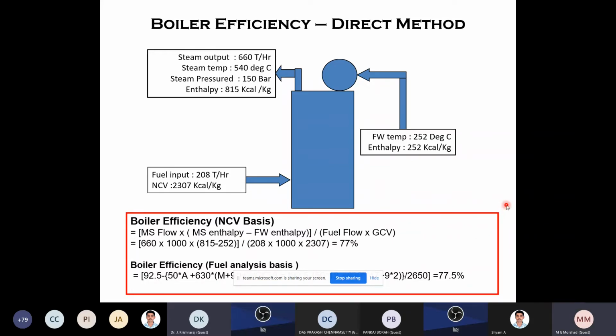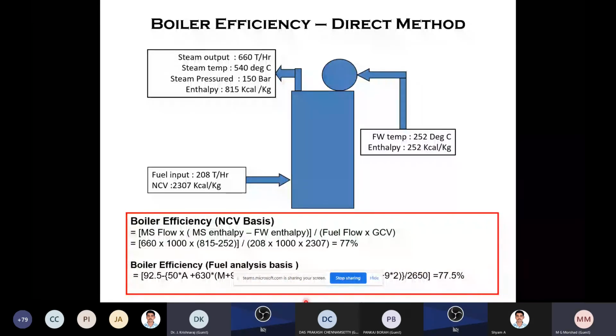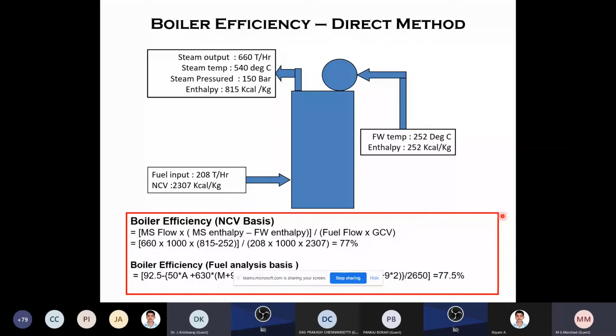One another method is the fuel analysis method, using the percentage of ash, moisture, and hydrogen. One formula is available here, and using this formula you can find it out. If you go for the fuel analysis, they will give oxygen, moisture, ash content, everything, and based on that you can carry out the efficiency. Is it clear? Yes, sir. Okay, now if you keep this picture in your mind, you can find out what parameters are required and how it can be calculated. Very easily you can calculate it.